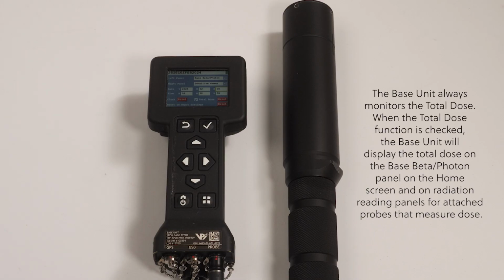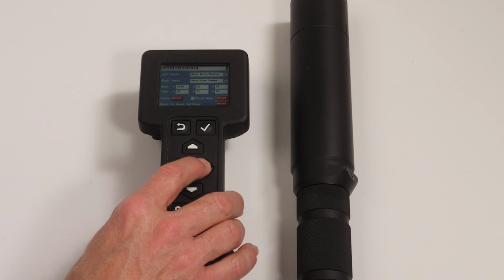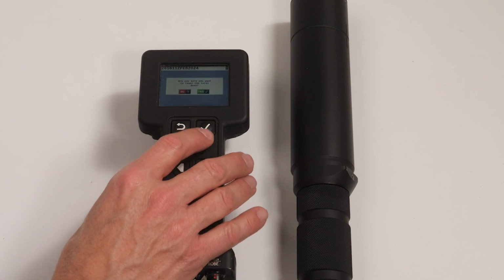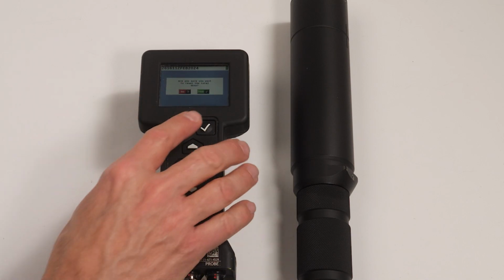The base unit always monitors the total dose. When the total dose function is checked, the base unit will display the total dose on the base beta/photon panel of the home screen and on the radiation reading panels for the attached probes that measure dose. The total dose amount can be reset to 0 by highlighting the reset button to the right of total dose and pressing enter.